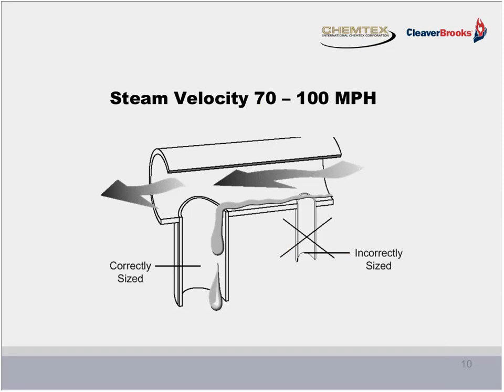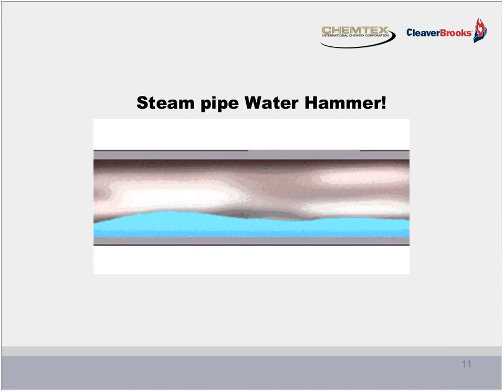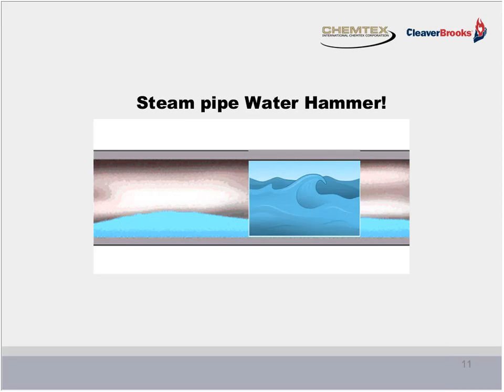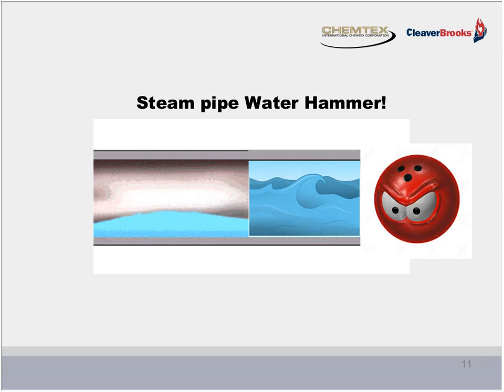Now, to combat the problem, steam lines are equipped with drip pockets to catch this condensate, but if the amount of saturated water exceeds the capacity of the pocket, or it is sized too small to begin with, this happens. A slug of water can wave up, actually plugging the pipe, speeding the water down the main at speeds close to 100 miles per hour. Now, be mindful. This main could be 14-inch in diameter or even larger, meaning the slug of water could equal a couple of gallons.